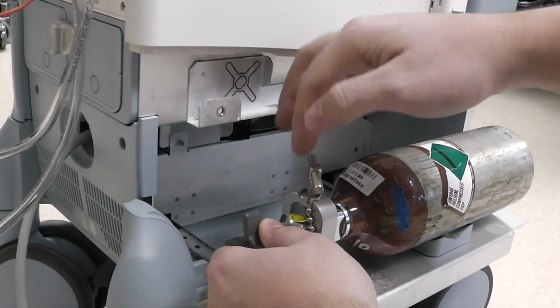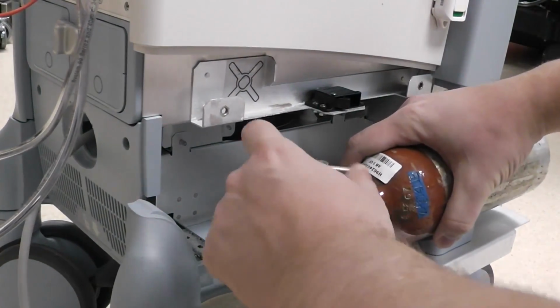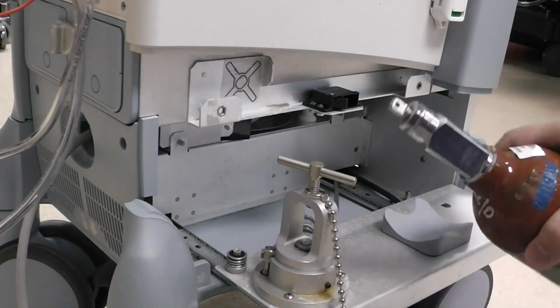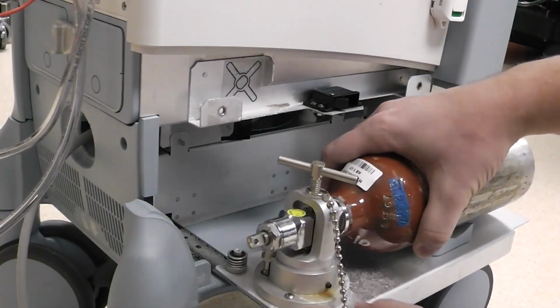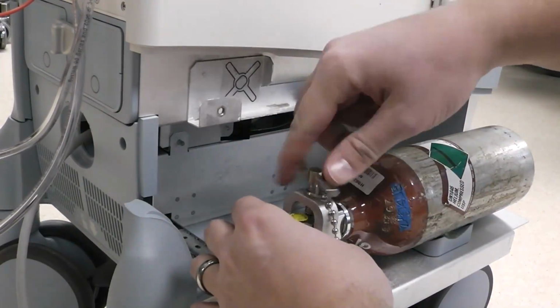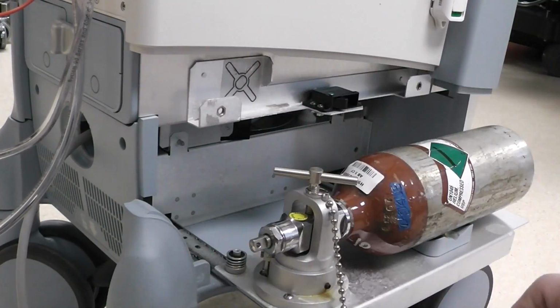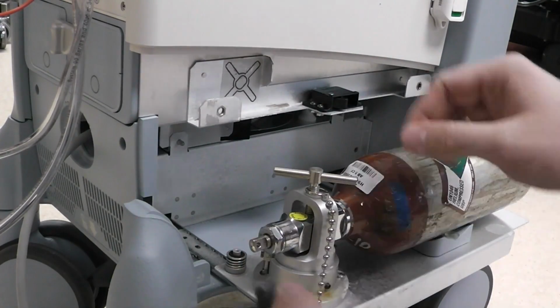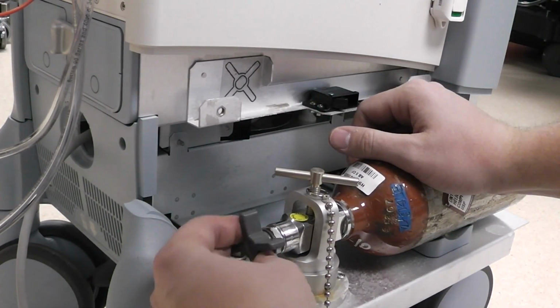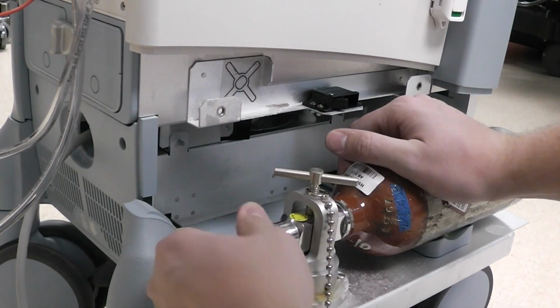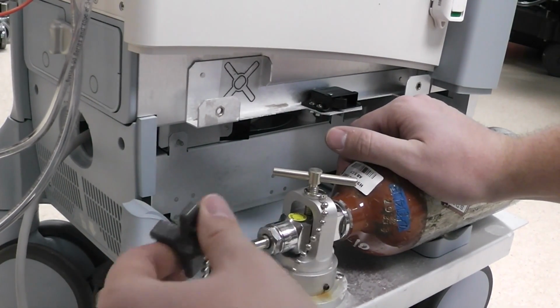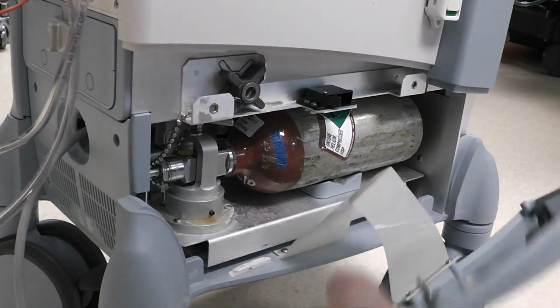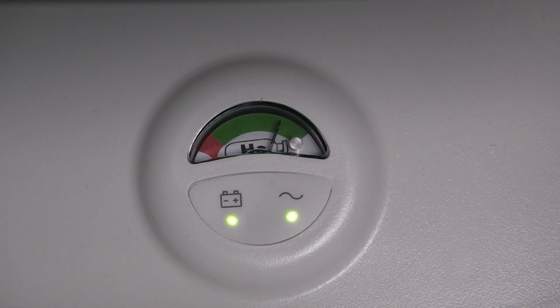Alright. Now you can remove that and remove the helium tank. Now you grab your new helium tank, put it back in, tighten this back down, make sure it's snug. You don't have to really crank it down, but make sure it's pretty snug. Then you can use this to once again open up the helium. You don't have to open it all the way, but a couple of turns should suffice. Then you can close that back up. And of course, after you've changed out the helium tank, make sure that the pressure you're receiving is adequate.